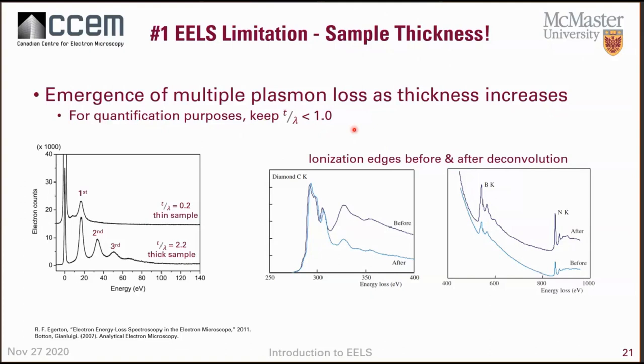If you have a spectrometer with dual EELS, I highly recommend acquiring the zero loss peak, or even without dual EELS, acquire the zero loss peak first. You can then ensure you've measured your sample thickness and know if the region of interest is suitable for EELS. Acquiring the zero loss peak is really fast — just a few seconds — and you can already see the thickness of your region of interest.